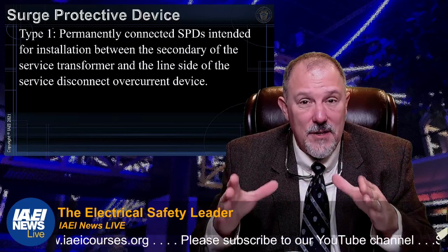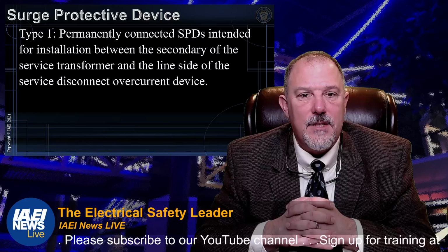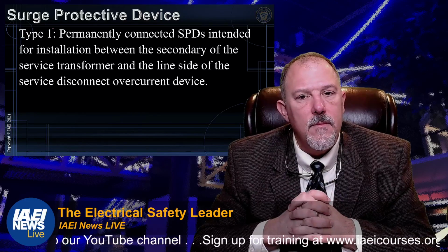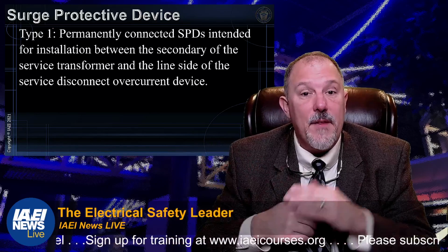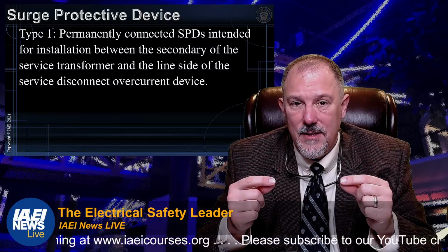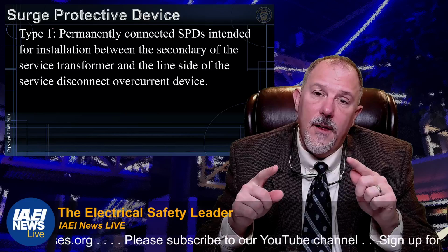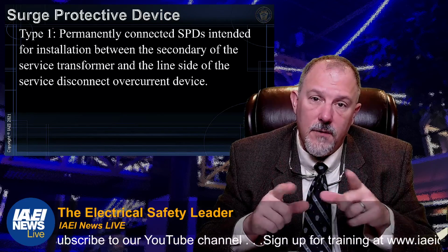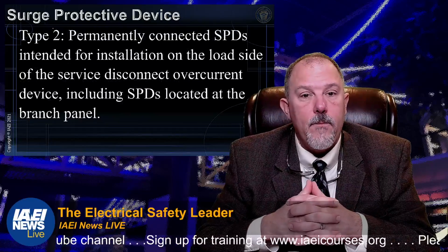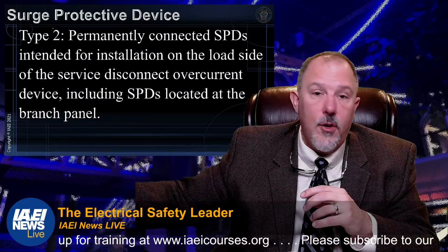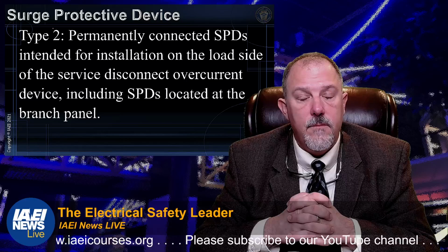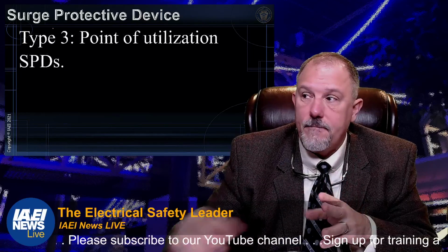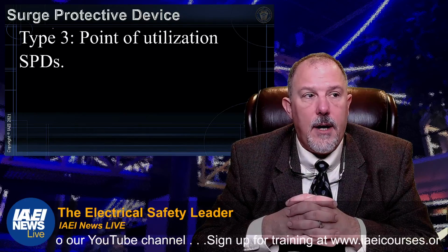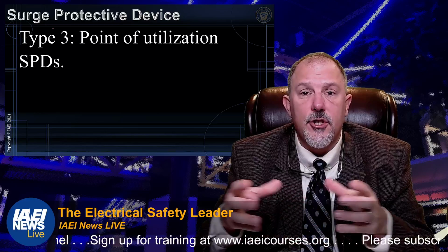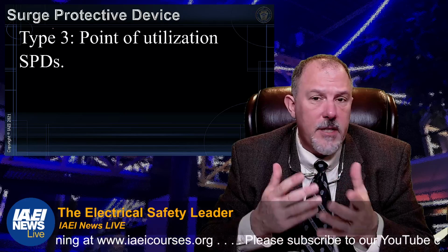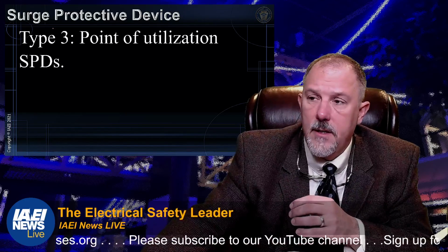So you have different types of surge solutions out there. Type 1 is permanently connected, intended for installation between the secondary of the service transformer and the line side of the service disconnecting means. So a type 1 device is installed on the line side of your service overcurrent protective device. A type 2 is on the load side of your service disconnect overcurrent device. A type 3 is at the point of utilization. I would say a good example of a type 3 would be a surge strip or a receptacle that has your surge protection built in. It's at the point of utilization. Maybe it's in a cord.